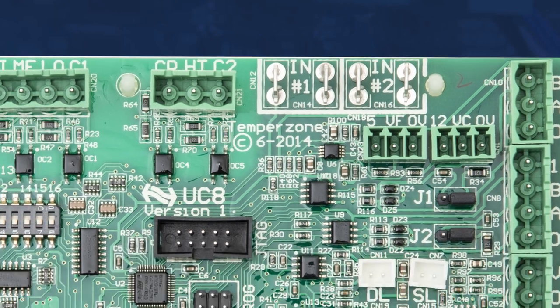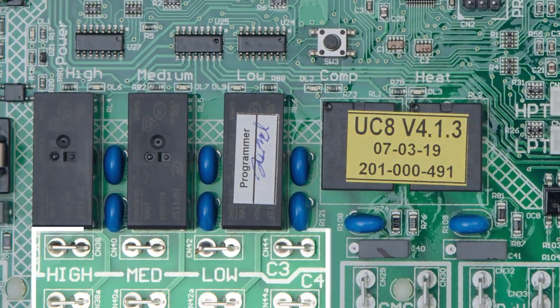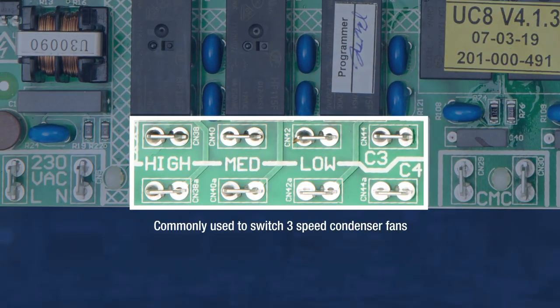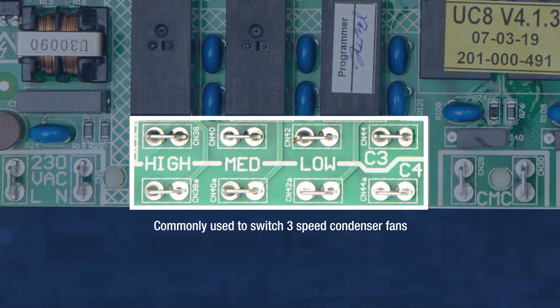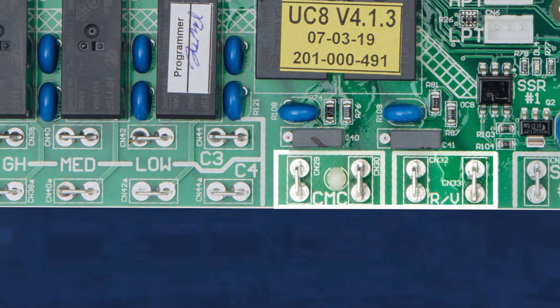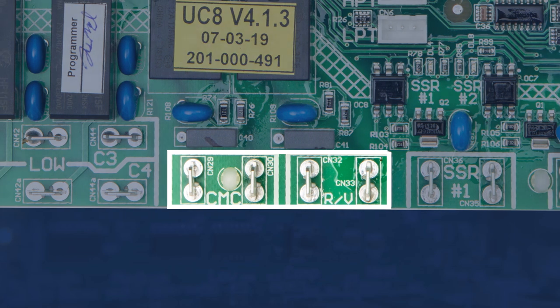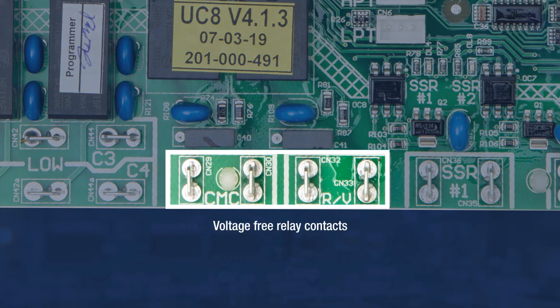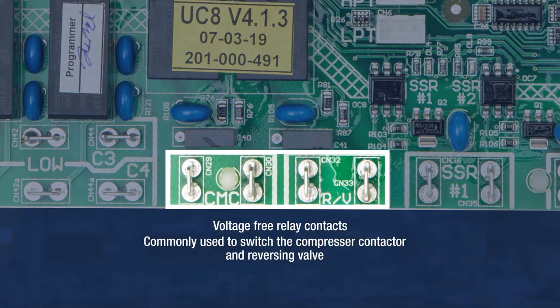Relay outputs high, medium, and low are commonly used to switch three-speed condenser fans, but they may also be used in other configurations to switch indoor fan contactors. CMC and RV are voltage-free relay contacts that are most commonly used to switch the compressor contactor and reversing valve.